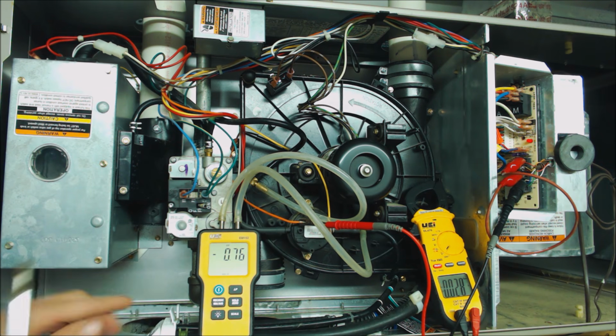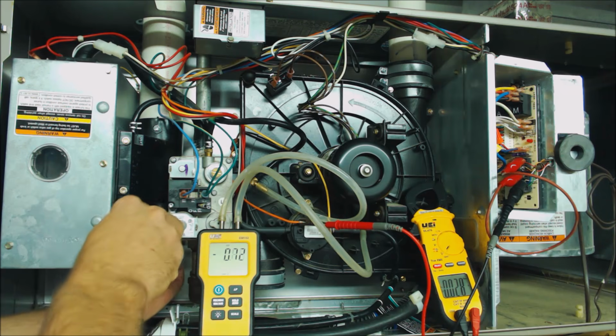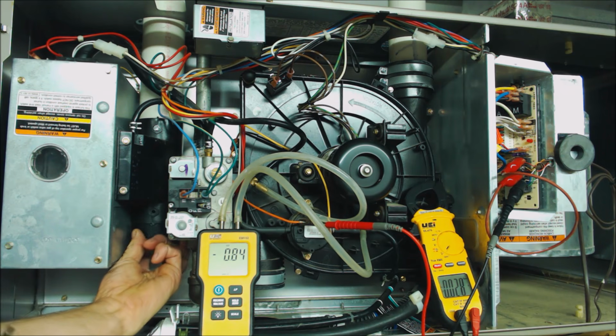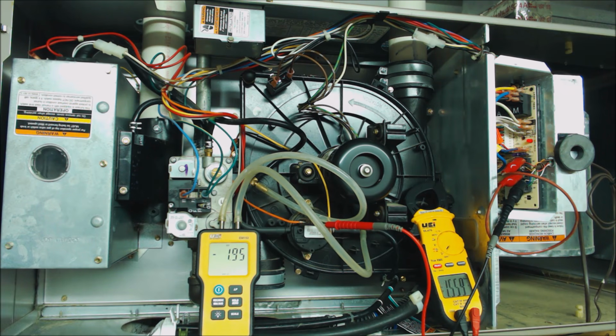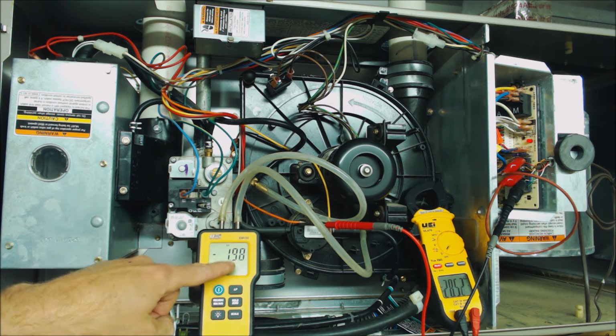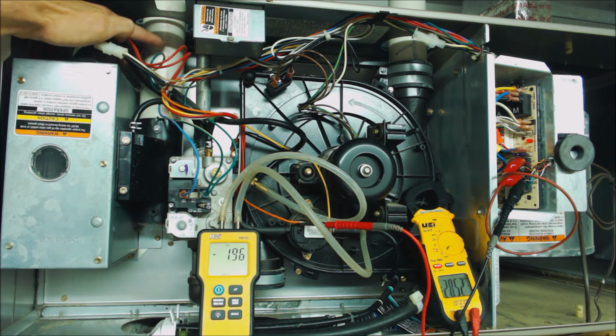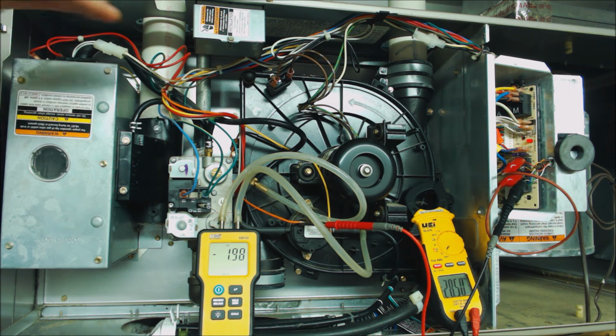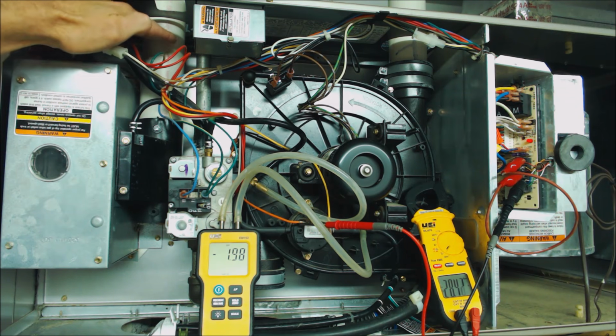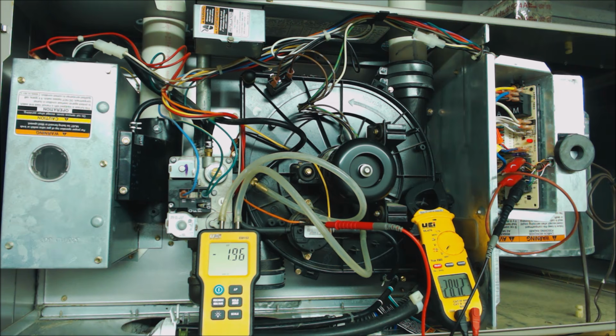So actually, you know what the problem is already? It's a clogged combustion air. So if I pull this out and it starts taking combustion air from within the room, now we actually have the correct differential. So this combustion tube must be clogged, or it's undersized or something. It is not allowing the combustion air over to this. It may be too long, but most likely it's clogged, or maybe it's clogged with a bird's nest or something like that. We're going to have to take that apart and fish through it and check it out.